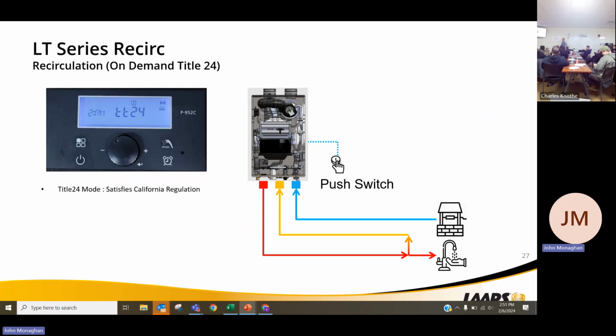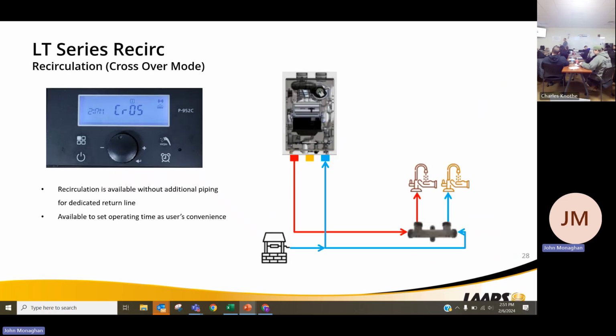So we're doing our Title 24. With Title 24, you're going to press that button. It's going to turn the pump on. You're going to recirculate your hot water for a set amount of time, usually up to a half hour, and it'll get your hot water there faster. Then the heater will take over, and you'll have hot water. Title 24, again, is mainly just on the West Coast. Your other option is going to be your crossover mode.